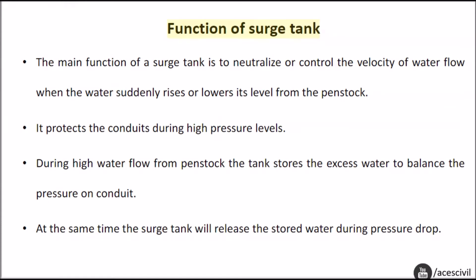Function of surge tank: The main function of a surge tank is to neutralize or control the velocity of water flow when the water suddenly rises or lowers its level from the penstock. It protects the conduits during high pressure levels. During high water flow from the penstock the tank stores the excess water to balance the pressure on the conduit. At the same time the surge tank will release the stored water during a pressure drop.